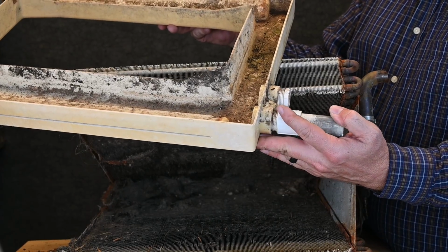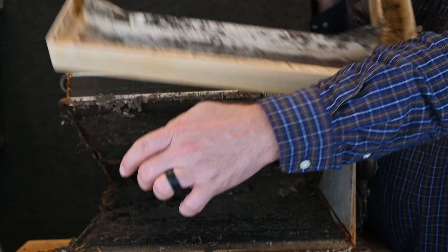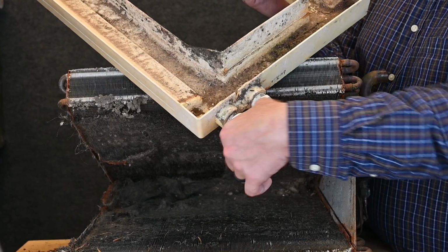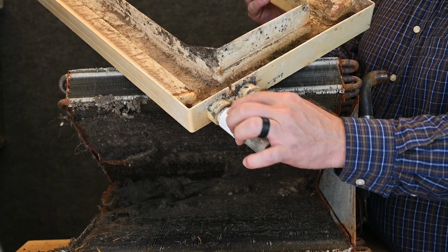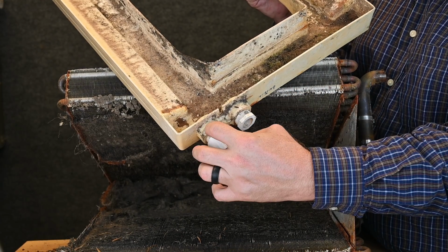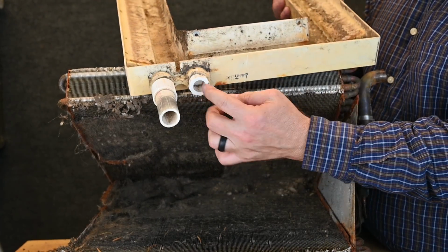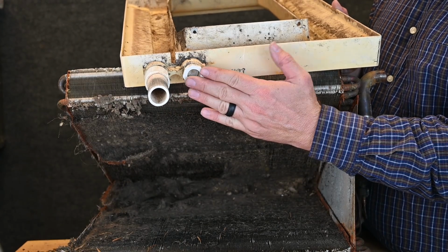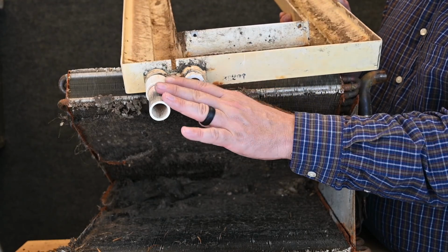To replace this drain pan, you have to take the whole entire evaporator coil out because there's two screws on the very, very back side holding it all together. So typically what I do is I tighten this up hand tight. I try not to use any tools on these at all, and it's not needed for most people. And also don't put any type of glue because all that does is bond it to where you can't get it back off to do any work in the future. And you also have two different ones. One is up higher than the other, so this is our primary drain, and this is going to be used for our overflow. We're going to talk about drains a whole lot later. It's just an introductory to that side.